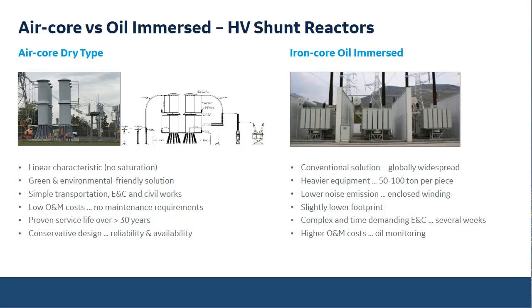There is no oil treatment, so an oil-filled unit may require days or weeks for oil treatment and inspection, gas inspection. The air core dry type has none of that. And basically, it's a maintenance-free technology. So you can run these reactors for 30 years with basically no maintenance.